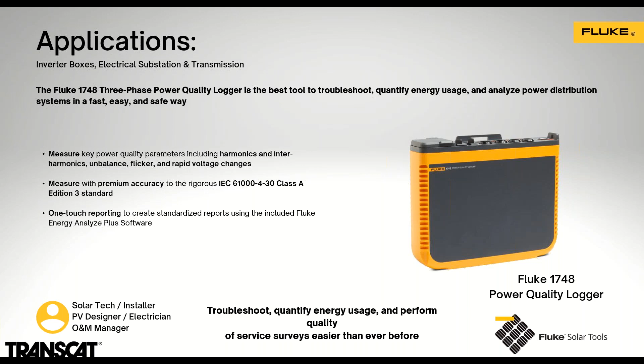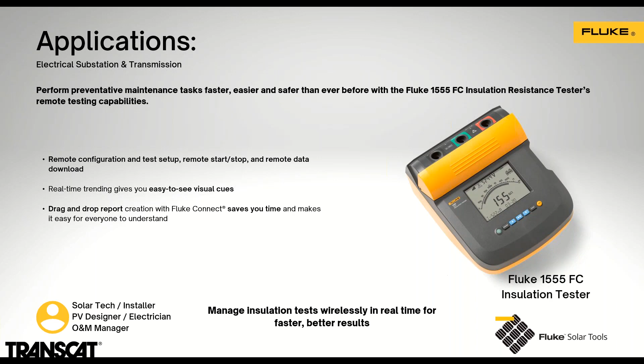And now with all of these connections, part of the commissioning aspect is to do insulation tests. So having some type of tool like a 1555 is going to give them the top end voltage output that they need to validate that those conductors have been installed correctly and that we don't have any insulation breakdown within that system. But this is also part of that reporting capability, and having the 1555 FC gives them that opportunity to grab that data, put it into their reports, and determine that the insulation tests were done correctly prior to commissioning.